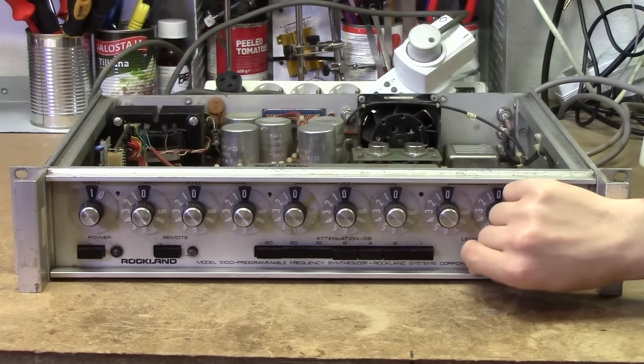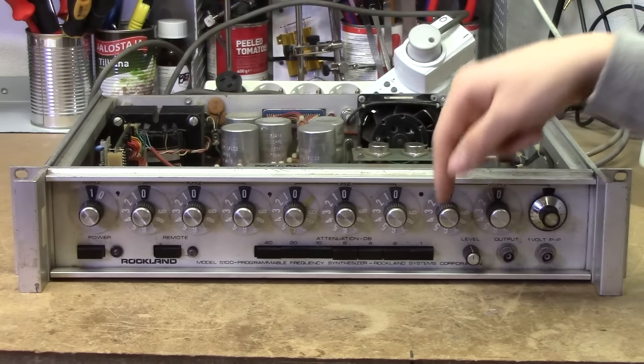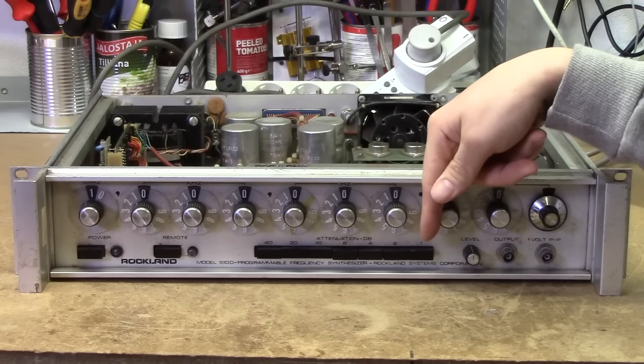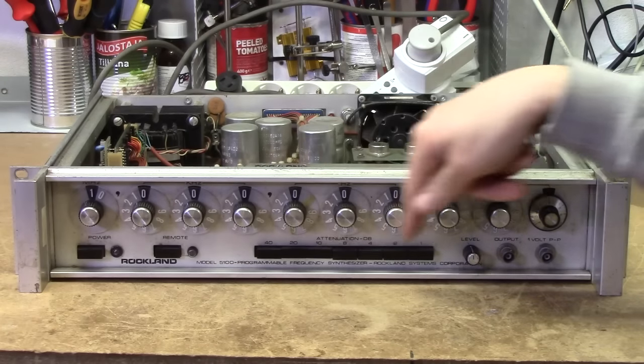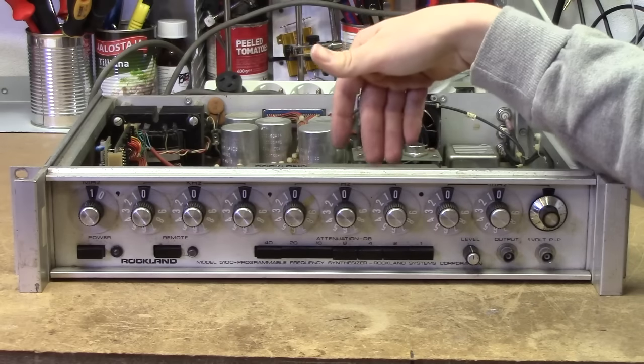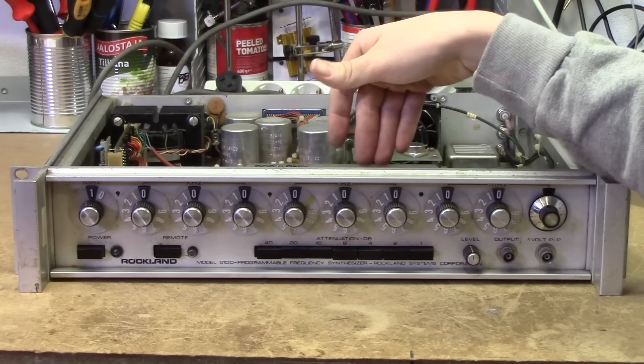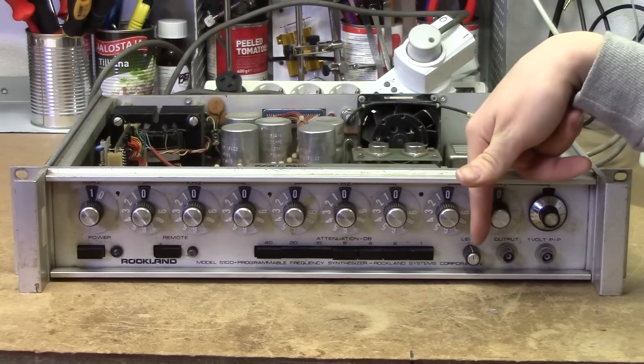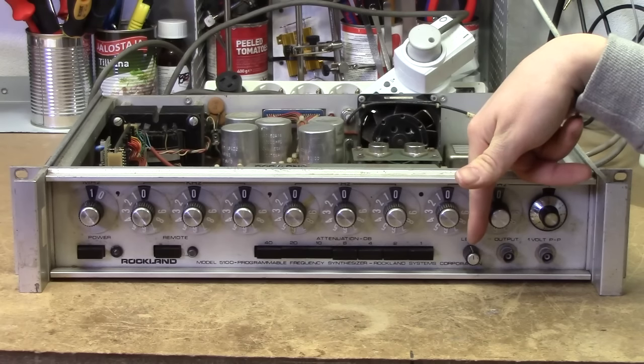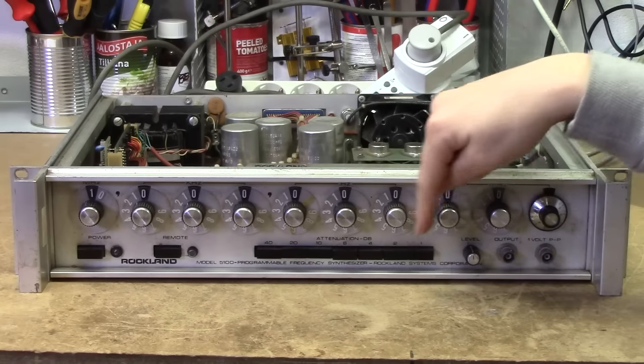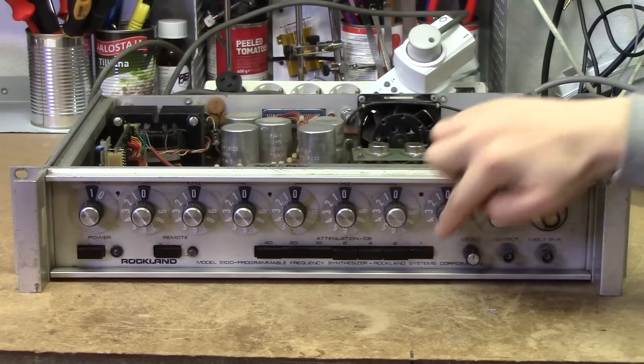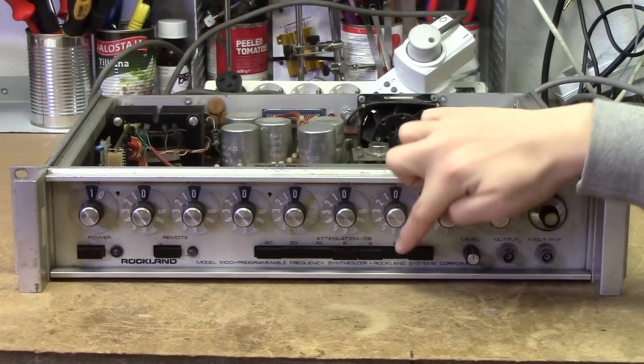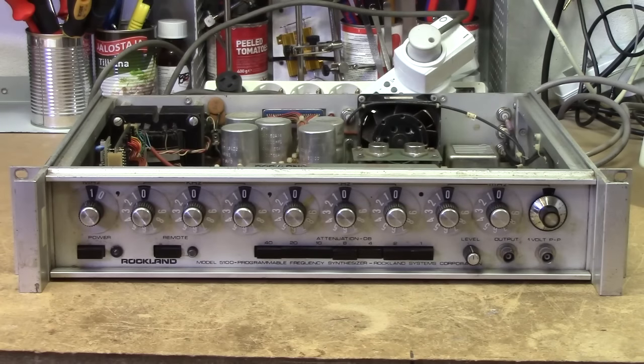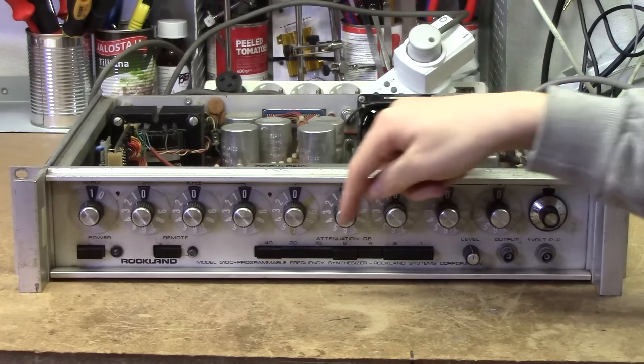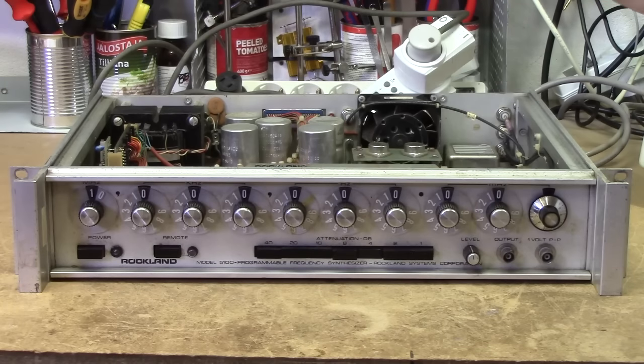The attenuator actually works. And we've got a decibel attenuator situated there, which is obviously using the attenuator board in there, whereas this one's just adjusting the gain of the output stage. And this one works perfectly. It's additive, so you've got 1 decibel, 2 decibel, 3 decibel, 4 decibel, so it comes out like a binary thing, except instead of going to 16 it goes to 10.